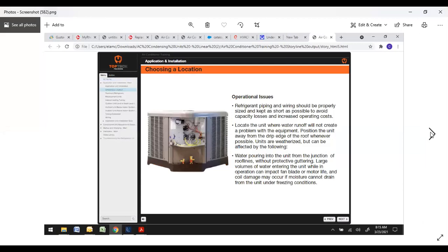So on installation, when you're choosing a location for a new air conditioner, a lot of times you don't have the option. You're putting it back to where the old one was, but you want to keep a few things in mind when you're finding that location. Refrigerant piping and wiring should always be properly sized and kept as short as possible to avoid capacity losses and increased operating costs. The further your line set goes, you will lose overall capacity after a certain point. So your 3-ton, for instance, is no longer operating at a 3-ton, and it will cost you more to operate. This is a big one for air conditioners and heat pumps especially.